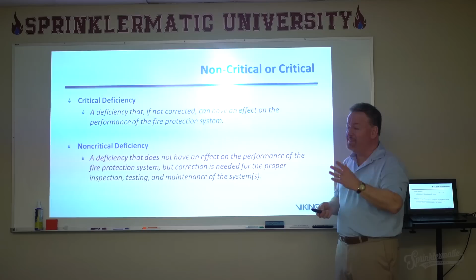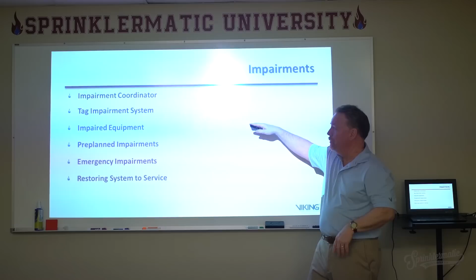If there is an impairment, if we say that system is impaired, the valve is closed, or I'm going to close the valve, or what have you, Chapter 15 comes into play. So we have to have an impairment coordinator, somebody to watch over that impairment, to follow through with the fact that the system is down. We're taking necessary safety precautions while it is down, and we're going to put it back in service. So somebody's got to be able to watch that. We have a tag impairment system, or an impairment tag system, that identifies those valves that have been closed.